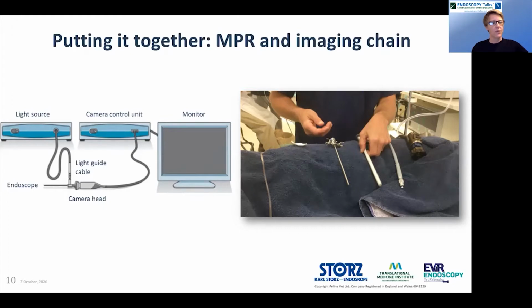We will typically also use a camera control unit, and that's attached to a CCD chip, which is in the camera head. And that's a way of taking an image from the field of view and digitally turning that into an image that's projected onto a monitor. Traditionally, we used to look through the oculus or the eyepiece just with your naked eye, but with a lot of the procedures these days, that would be considered pretty unhygienic. And I know with a lot of cases that I do see, I wouldn't want my face near half the snotty cats that I see. So I would advise getting a digital system that you see here.